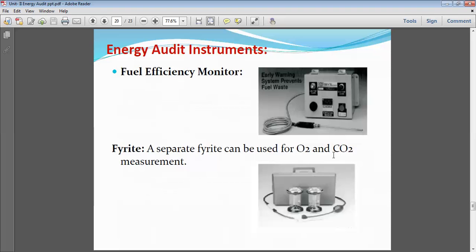This fuel efficiency monitor indicates how effectively we are utilizing fuels — whether oil, diesel, petrol, or coal — and whether the fuel is properly burned in the burning section. This fuel efficiency monitoring system can be used for boilers. Separate sensors can be used for O2 and CO2 measurements, so we can measure the individual quantity of O2 and CO2 in the boiler section.